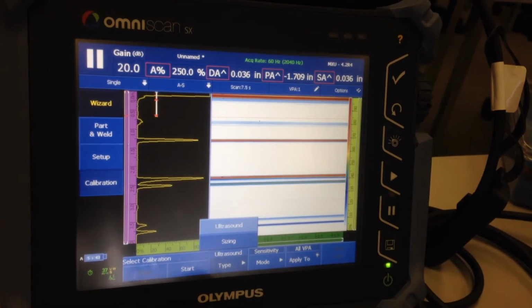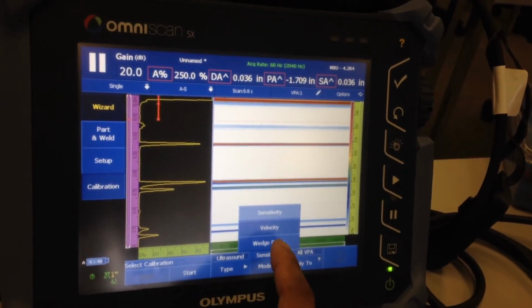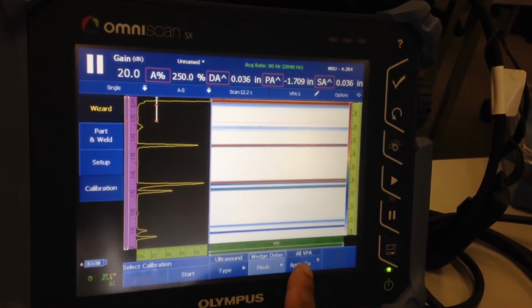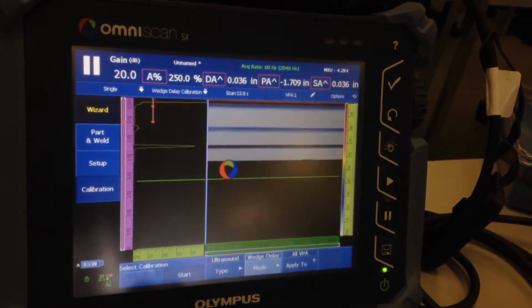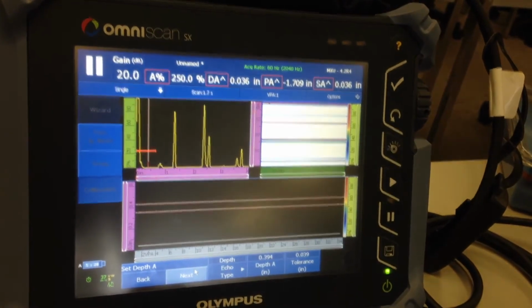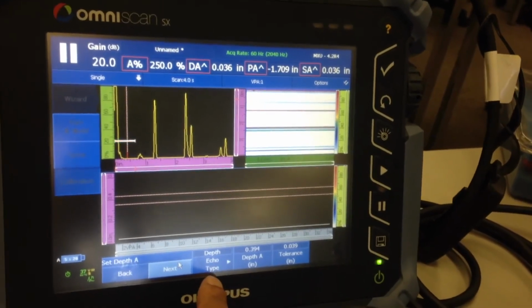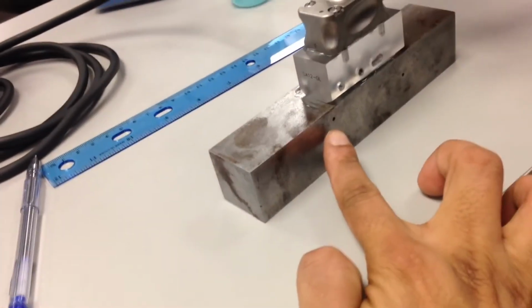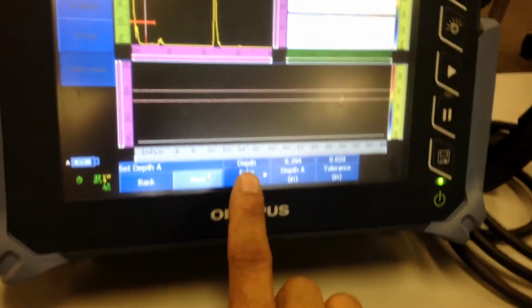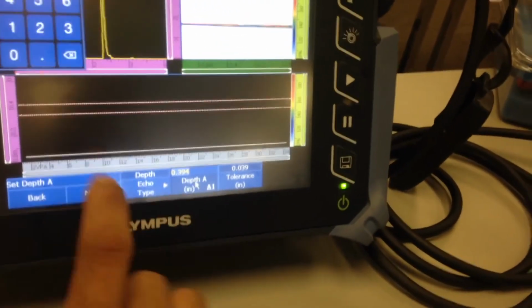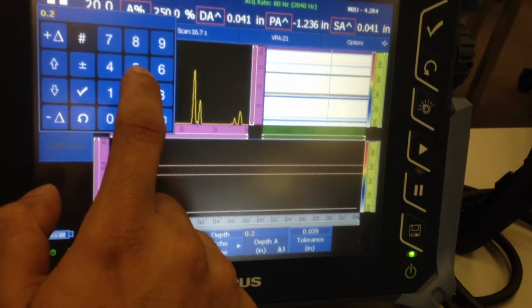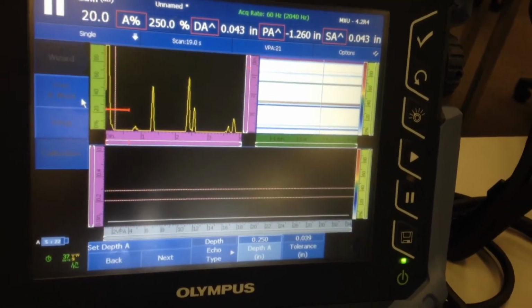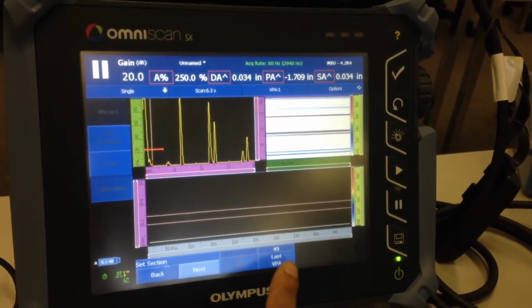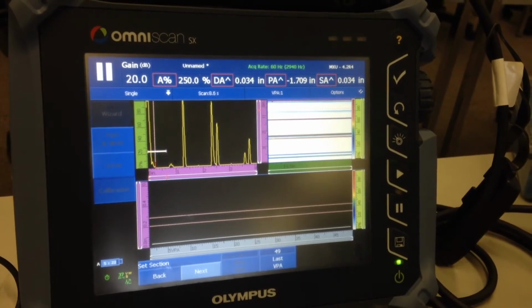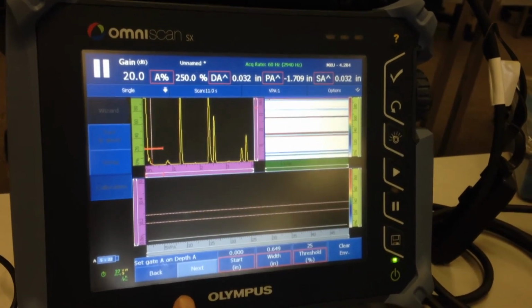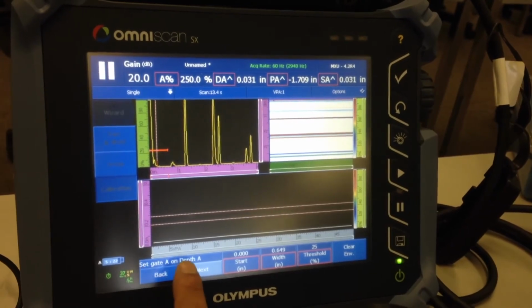So ultrasound, mode, wedge delay. Then start. Echo type, depth. In this case I'm getting a signal off of the 1/4 inch side drill hole. So my echo type is depth, and the depth is 1/4 inch. Click Next. First one, last 49. Click Next. Set gate A on depth A.